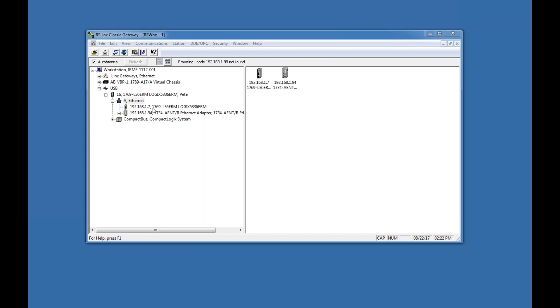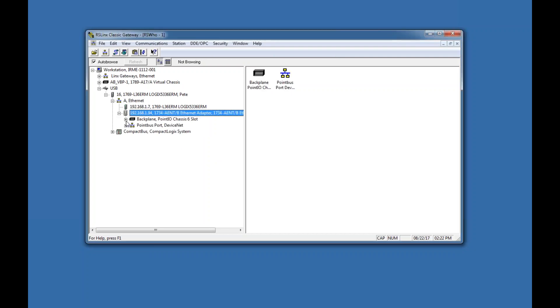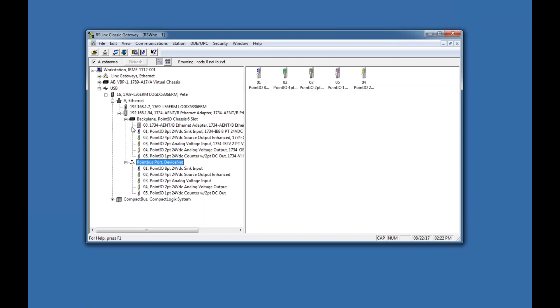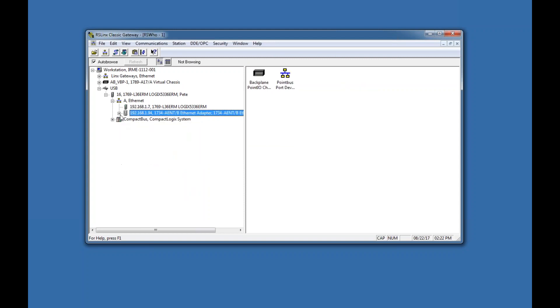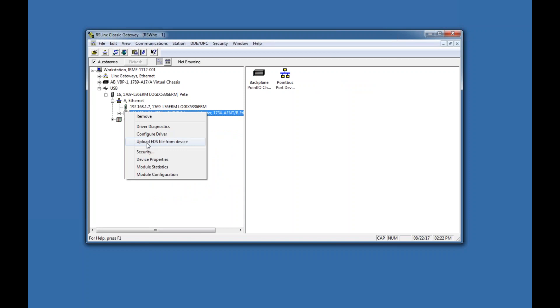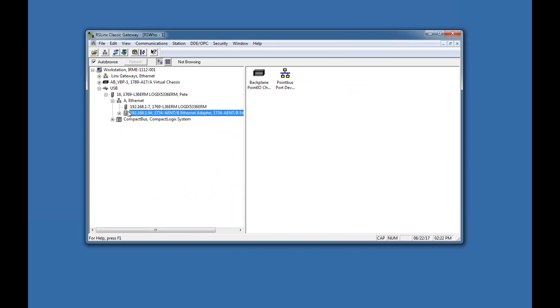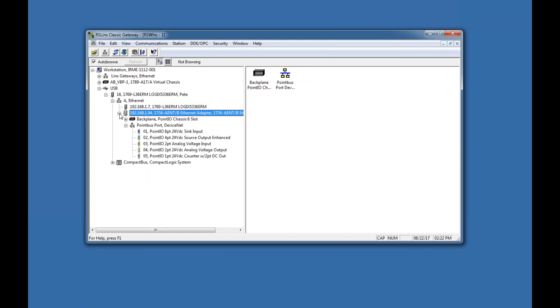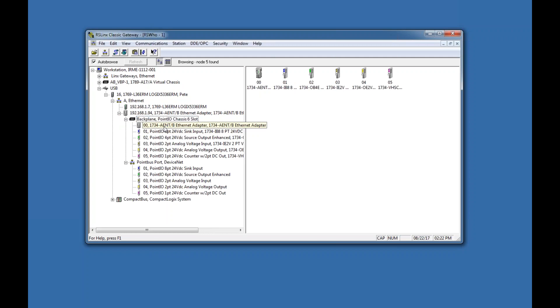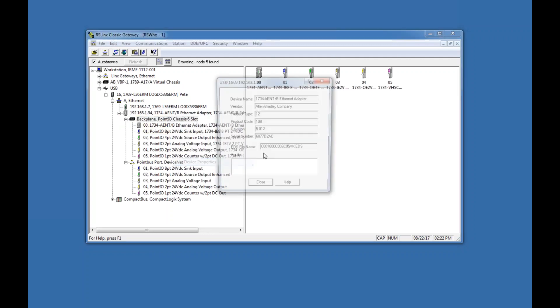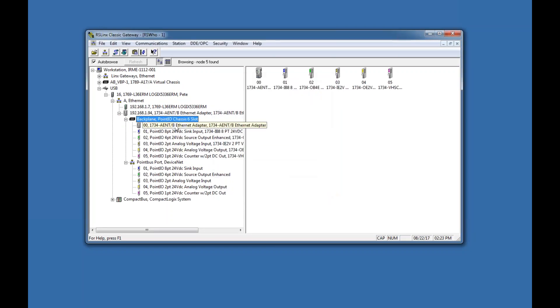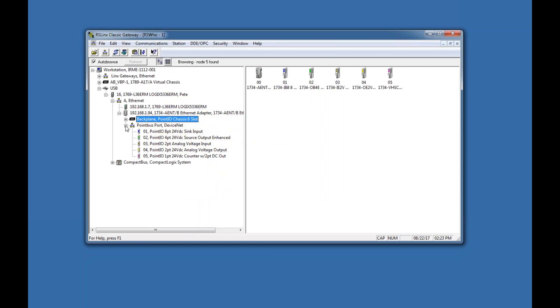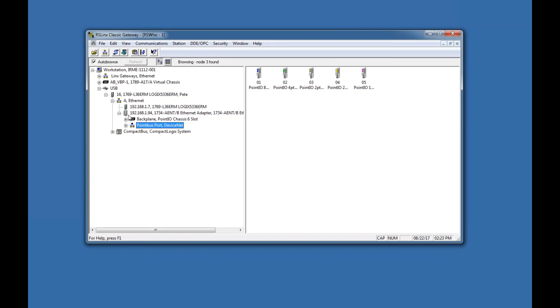There it is — it finally showed up. If I expand this, you can see the Point IO and any DeviceNet that's there. When you first get this out of the box, you may need to right-click and upload the EDS (Electronic Data Sheet). If a device isn't recognized, it will show up as a yellow question mark and you won't be able to view the Ethernet adapter properties or determine input/output configurations.